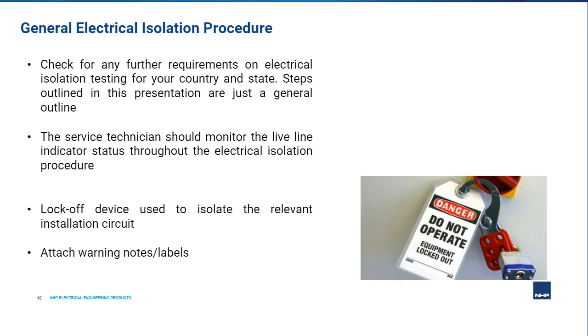Now, I did say at the start that these were general steps to consider as part of the electrical isolation process. You need to check your country or state's standards on the complete electrical isolation procedure and ensure that they are followed. The status of the liveline indicator should be monitored regularly throughout this process to ensure the safety of the operator. Once you've established electrical isolation, it's generally required to lock off the isolation device or devices which were used to isolate relevant installation circuits. And then after that, warning or cautionary notes also generally need to be attached so that others in the facility are aware not to come into contact with them.